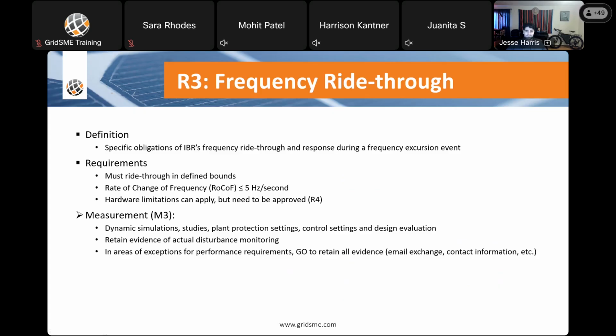All right, requirement R3, frequency ride-through. Very similar to requirement R1, except it's for frequency instead of voltage. The definition is specific obligations of IBRs' frequency ride-through in response during a frequency excursion event. So your facility is going to be required to ride through defined bounds, which I'll define in the next slide. Rate of change of frequency needs to be less than or equal to 5 hertz per second. And hardware limitations can apply, but again, need to be approved within requirement R4.